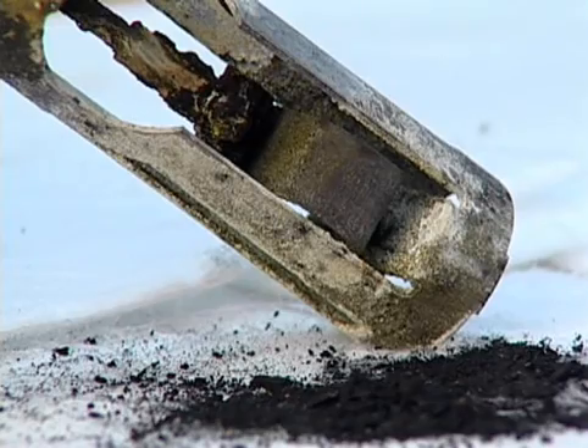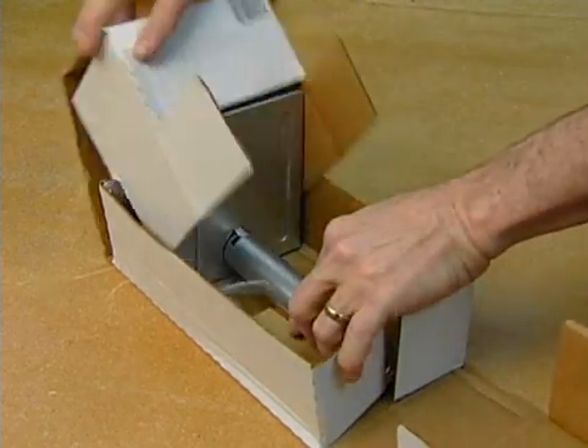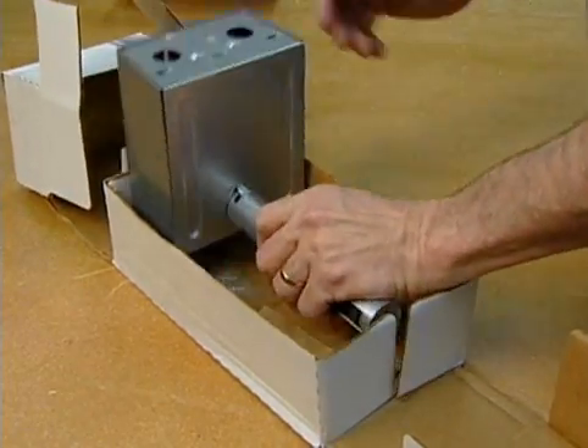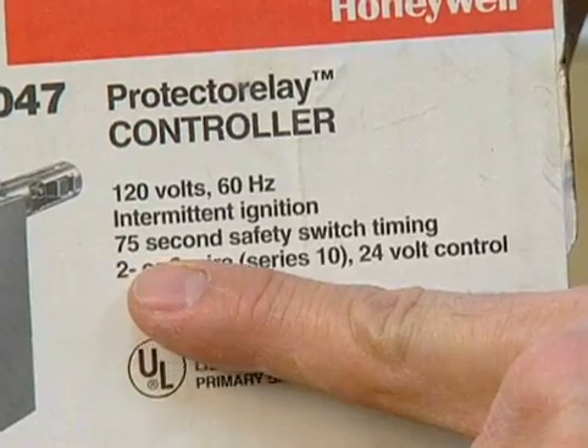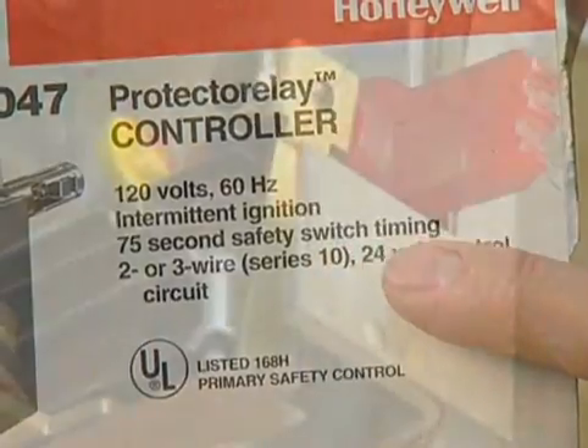If it checks out, clean the bimetal before reinstalling it. If the control does not go off on safety within 120 seconds, replace it and be sure to check the timing on the new control.